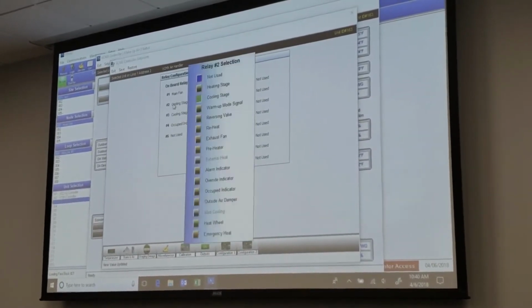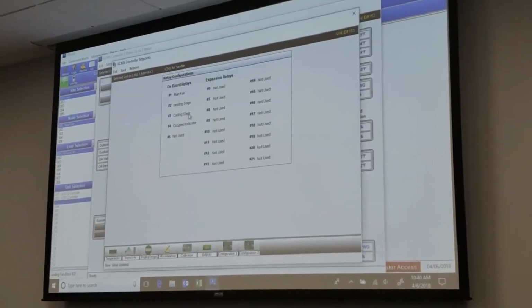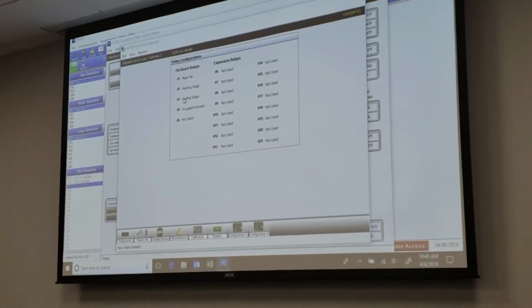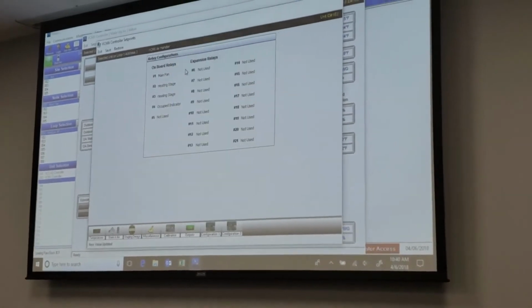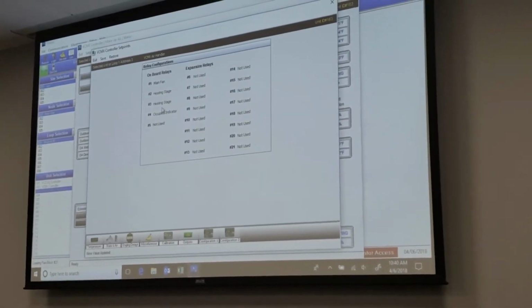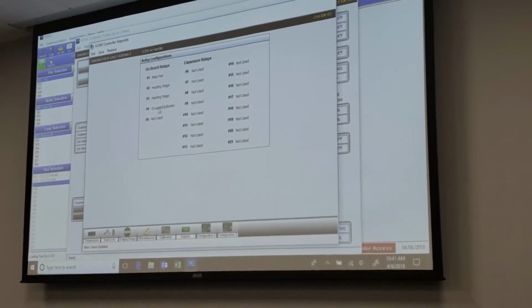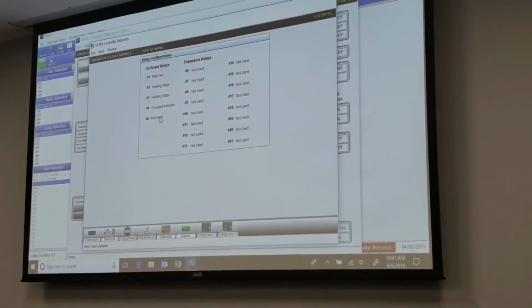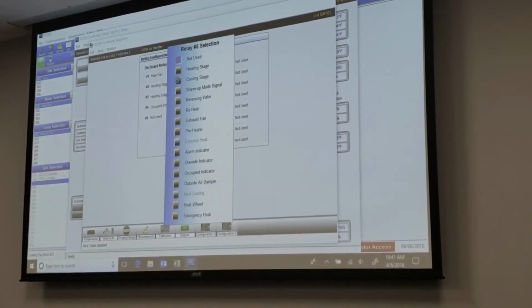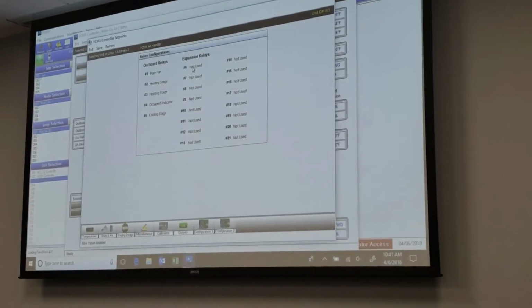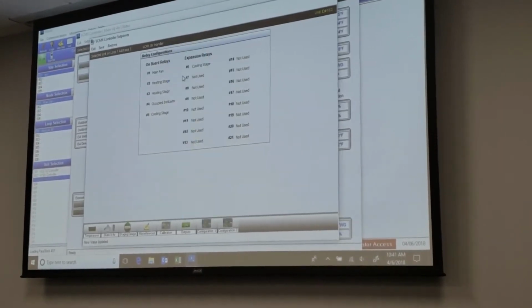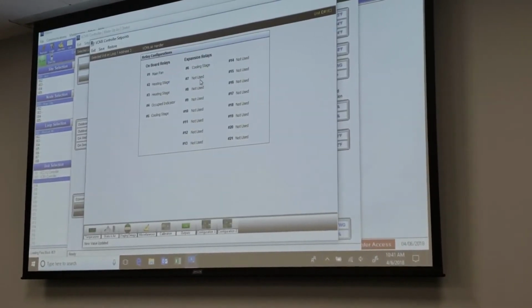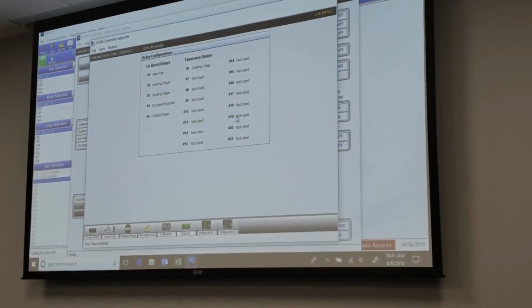Let's say this guy needs to be a heat stage. Occupied indicator. Anytime that board goes occupied, that relay will fire off. We can make these guys the cool stages. So if you have relays that go bad, you can actually move them over, just move them over to different relays that are not being used.